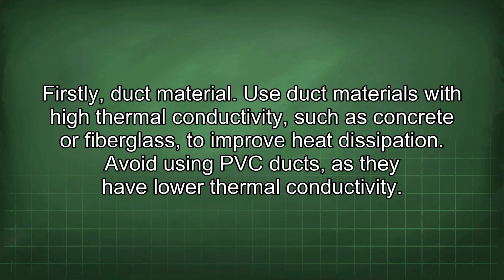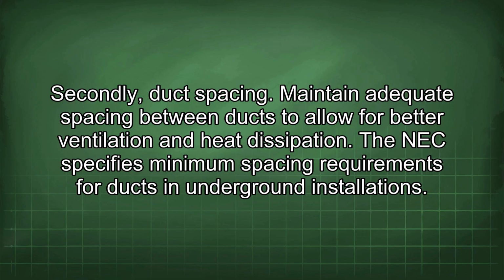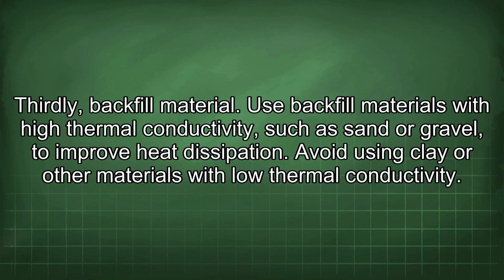Firstly, duct material. Use duct materials with high thermal conductivity, such as concrete or fiberglass, to improve heat dissipation. Avoid using PVC ducts, as they have lower thermal conductivity. Secondly, duct spacing. Maintain adequate spacing between ducts to allow for better ventilation and heat dissipation. The NEC specifies minimum spacing requirements for ducts in underground installations. Thirdly, backfill material. Use backfill materials with high thermal conductivity, such as sand or gravel, to improve heat dissipation. Avoid using clay or other materials with low thermal conductivity.